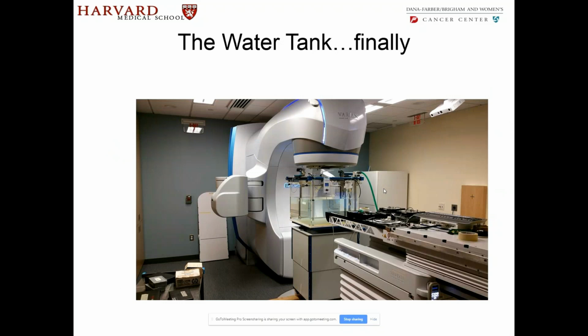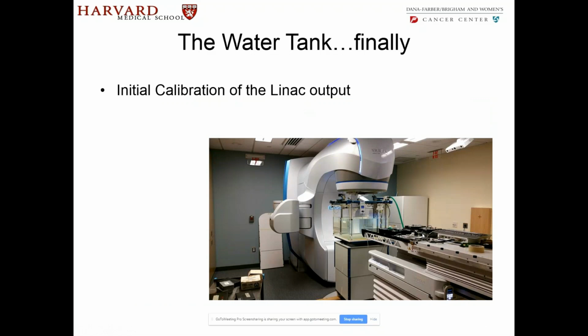The next stop is to actually start taking data. This is the exciting part. At least that's what I feel. The water tank, it's there finally. We have placed it in position, and we have the machine all ready to go. So the first thing that you do is you actually do an initial calibration of the Linac output. What that means is when these Linacs, they actually are pulsed. It's not like a continuous beam, as many of you are aware. It gives out photons in pulses. Now, as that is happening, how much does, it's not exactly a pulse, but I'll use the word because it's more intuitive. How much does each pulse correspond to in terms of dose, which is being given to water and equivalently to tissue when the patient is in position?